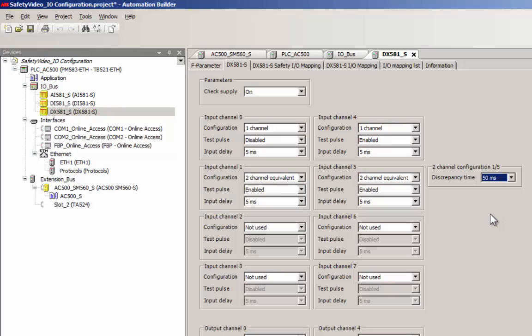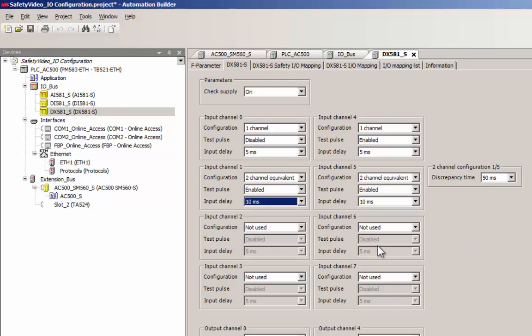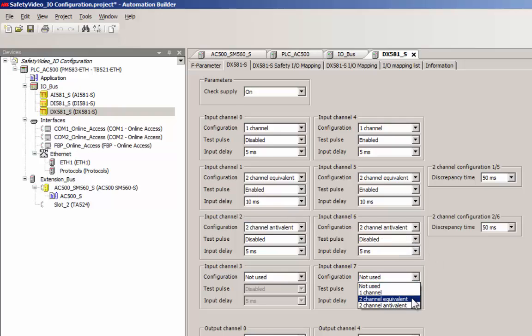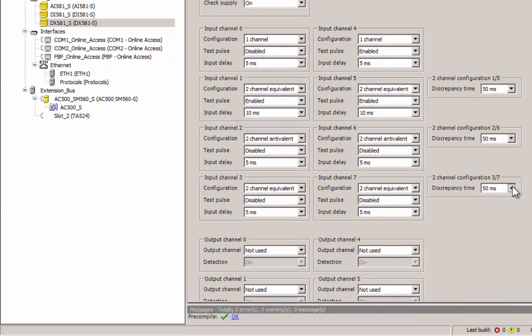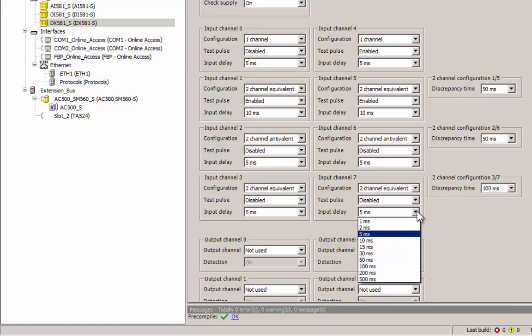If a sensor is powered from the module's test pulse output, then the test pulse option must be enabled. Appropriate input delay value must be set according to the input device response time in order to prevent channel passivation. Input delay setting acts like a low pass filter to avoid frequent signal changes being sensed by the module.